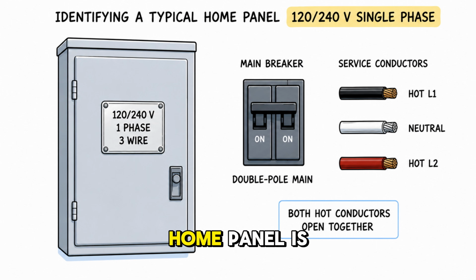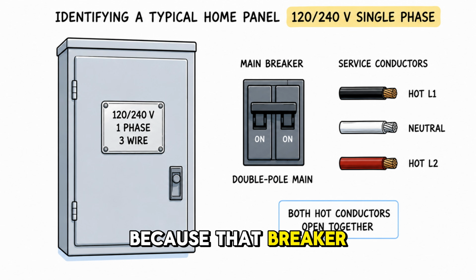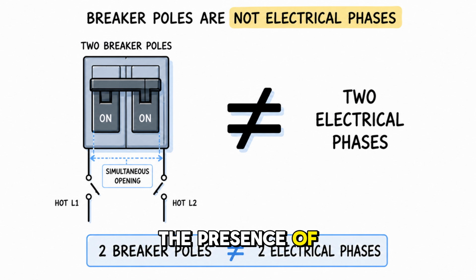A typical detached home panel is labeled 120 and 240 volts, single phase and three-wire. It normally has a double-pole main breaker because that breaker must disconnect both hot conductors. The presence of two connected breaker poles does not mean the panel has two phases. It only means both hot conductors must open together.